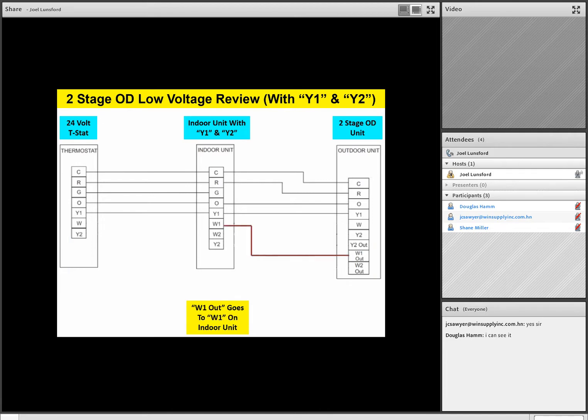Now remember that auxiliary heat could be a dual fuel system where the indoor unit's a furnace, or it could be a variable speed air handler in our example that has a Y1 and a Y2 terminal. So W1 out from the outdoor unit comes in and hooks up to W1 on the indoor unit. W2 output on the outdoor unit comes in and hooks up to W2 on the indoor unit. And then Y2 out from the outdoor unit comes in and hooks up to Y2 on the indoor unit.